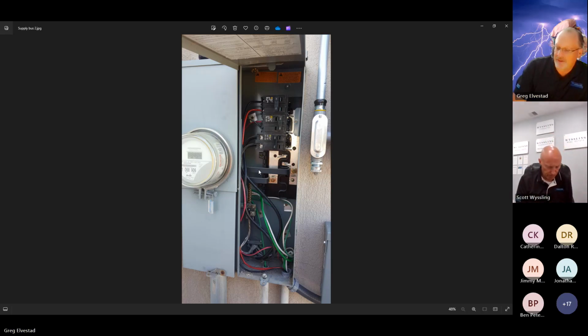Now, you see these three breakers. Well, they say, well, that's the disconnect for the house. Well, not necessarily. It is a disconnect for a load center, but it is not a disconnect for the service. There is nothing to turn off the power between a connection here and this meter socket short of pulling the meter. That's the definition of a supply bus, where your interconnection capability is equal to the rating of the service.